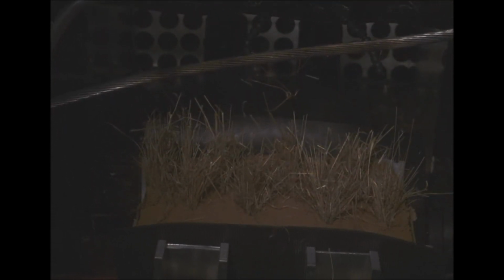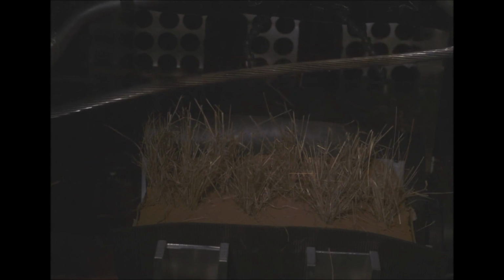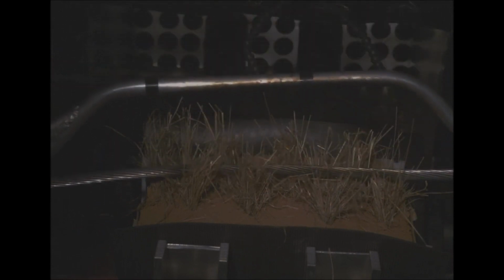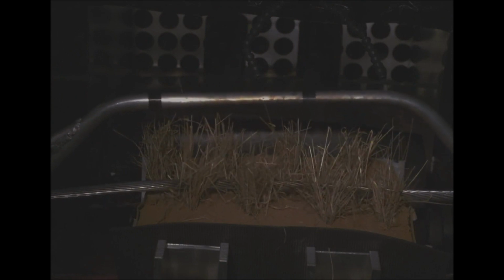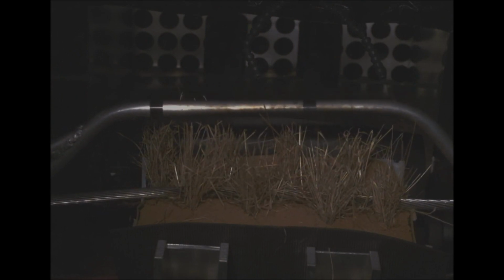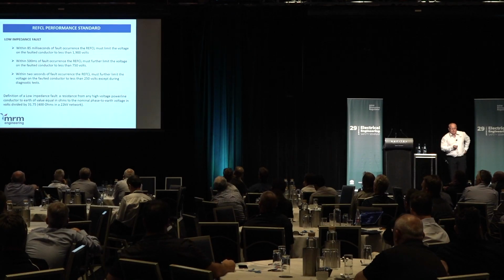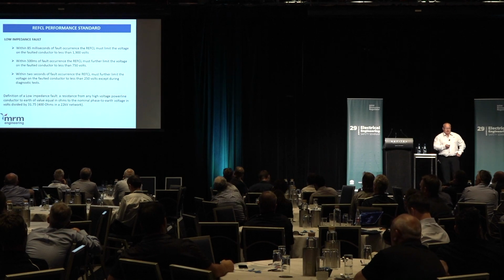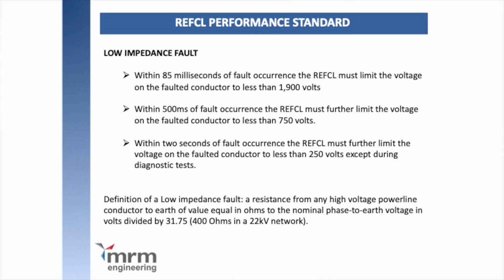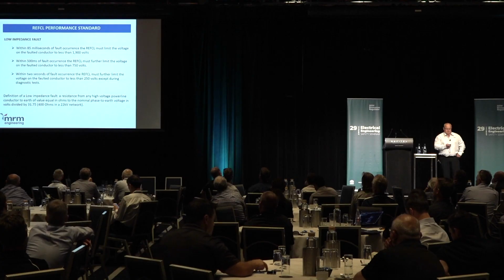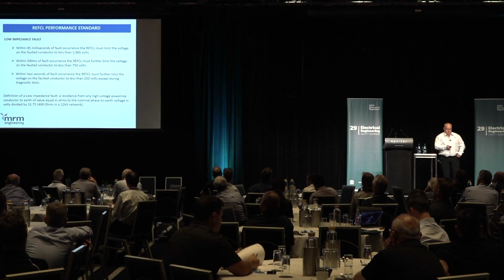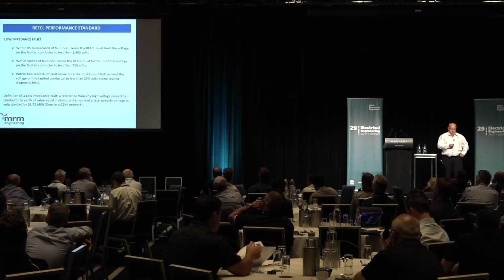So you can see from the ground fault neutraliser the sparks that occurred, the amount of damage or scorching of the grass was next to nothing, because the ground fault neutraliser or the REFCL system actually stopped the current flow. So they come up with the performance standard for a low impedance fault, 85 milliseconds. The fault must be limited to less than 1900 volts, 500 milliseconds to get down to 750, and then 2 seconds for the 250. The definition of the low impedance fault there is 400 ohms for a 22 kV network.